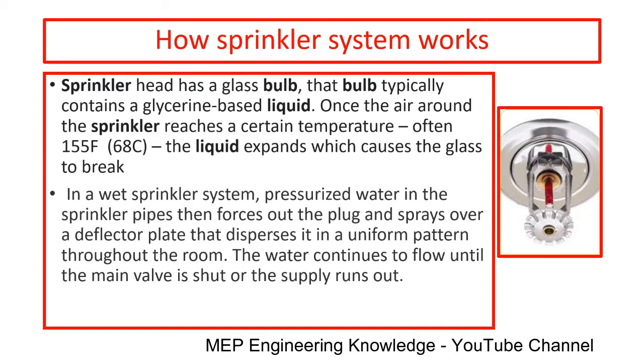Let us see how the sprinkler system works. The sprinkler head has a glass bulb. That bulb typically contains a glycerin based liquid. Once the air around the sprinkler reaches a certain temperature, often 68 degrees centigrade, the liquid expands, which causes the glass to break. In a wet sprinkler system, pressurized water in the sprinkler pipes then forces out the plug and sprays over a deflector plate that disperses it in a uniform pattern throughout the room. The water continues to flow until the main valve is shut or the supply runs out.